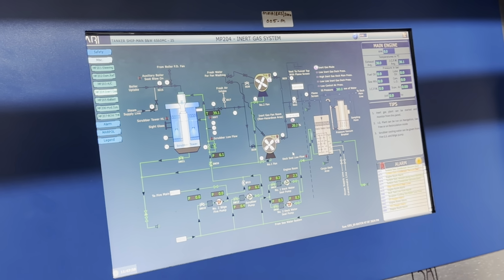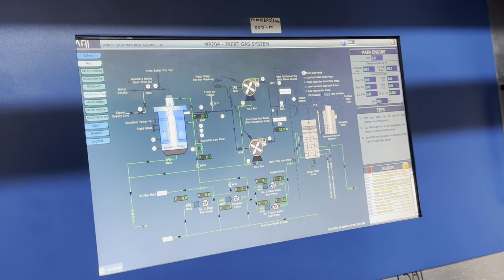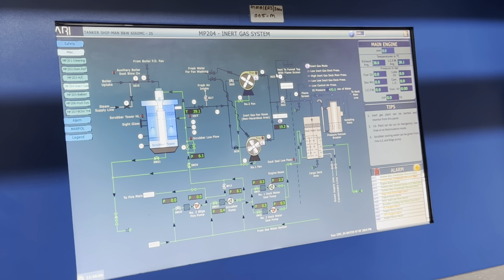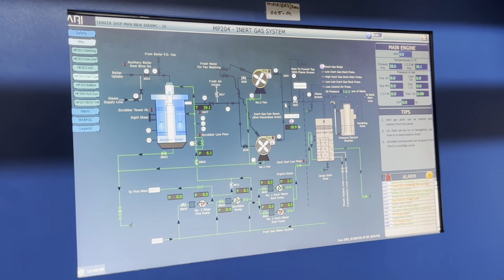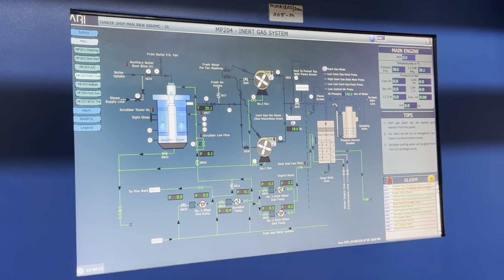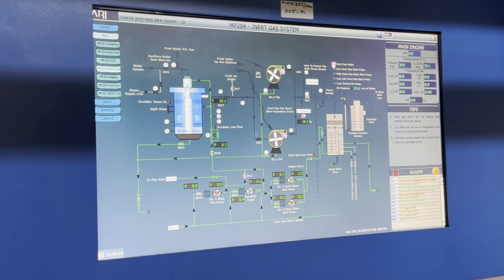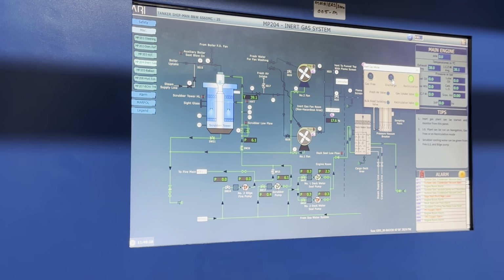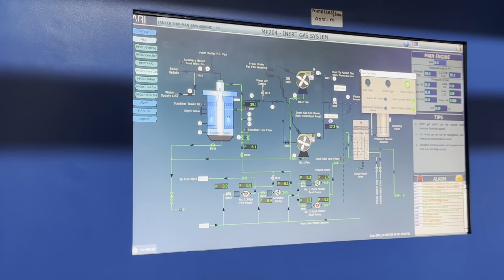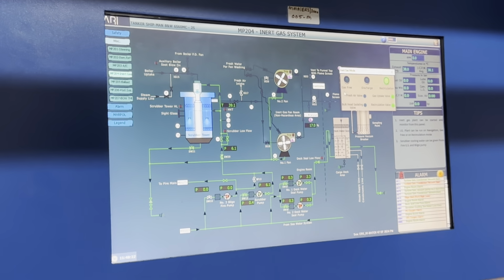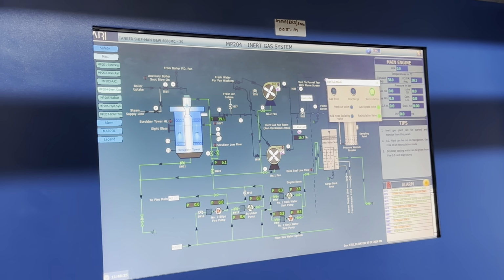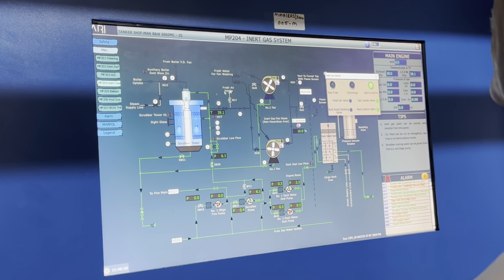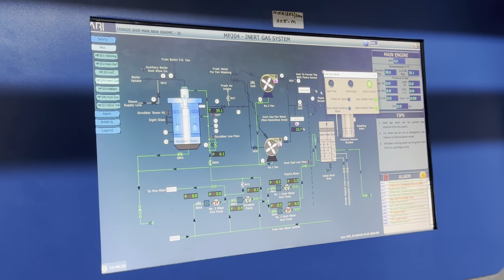Now you see the IG fan is running, and because the O2 percentage is high, it is discharging to the atmosphere through the funnel. You cannot put it to the inert gas mode. You cannot change it to discharge, it is already only on recirculation. And when we want to gas free a tank, in that mode we need to open the air valve for suction, the fresh air intake. Can you see here? Yes. Then the uptake valve is not open, and the fresh air is sent here.